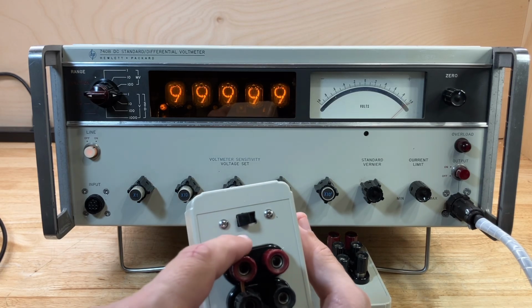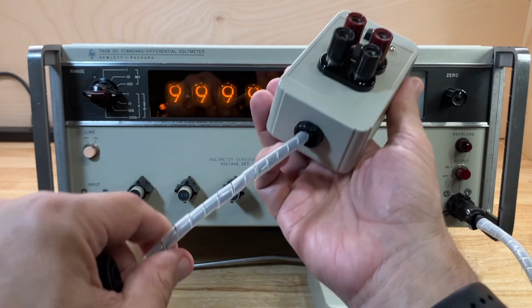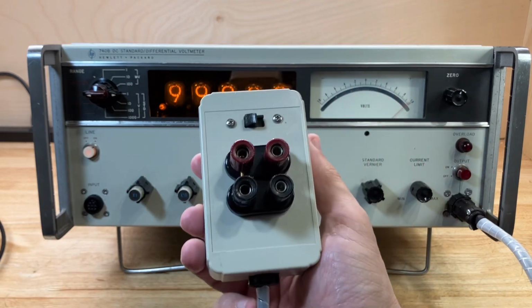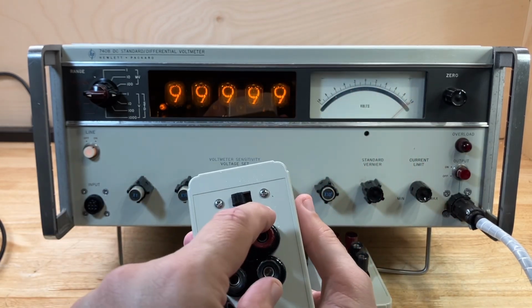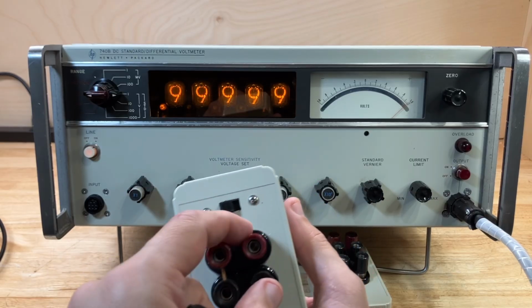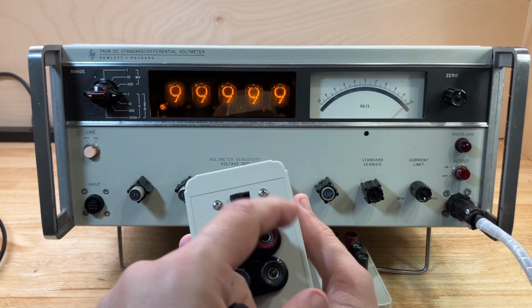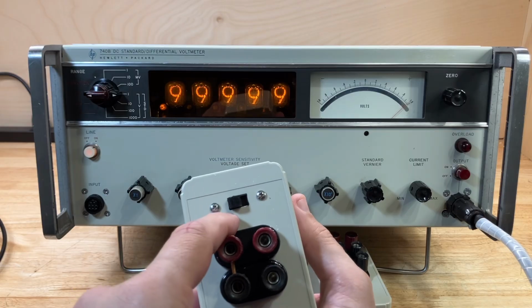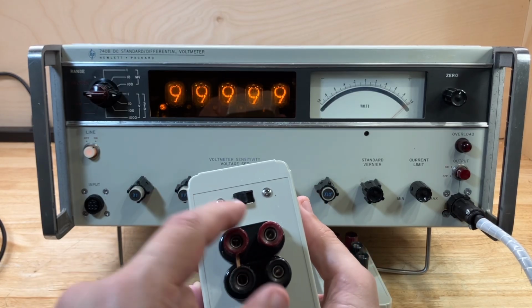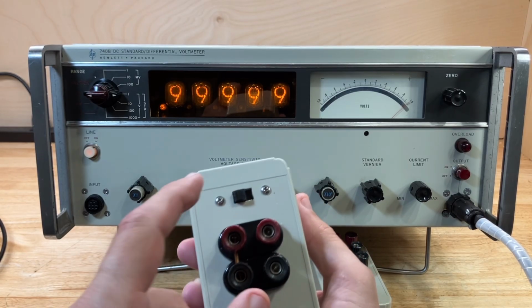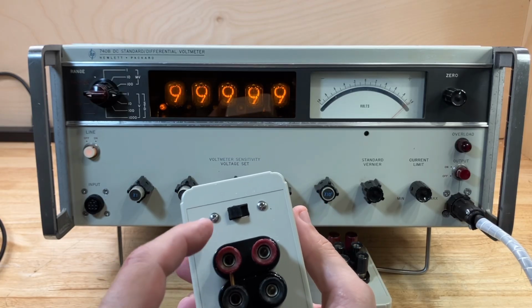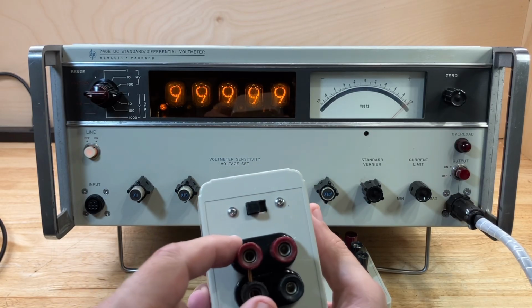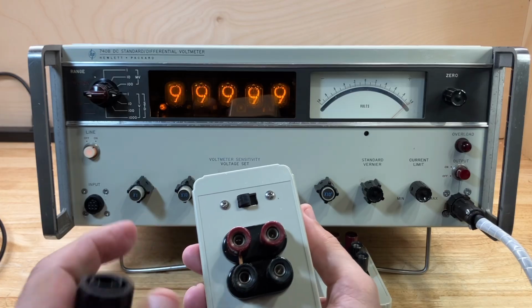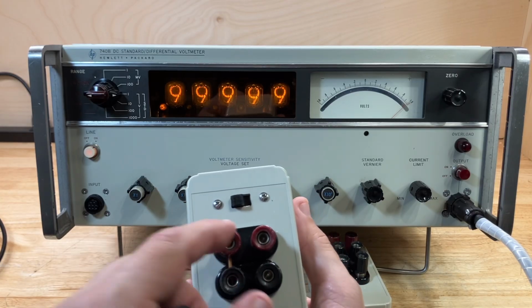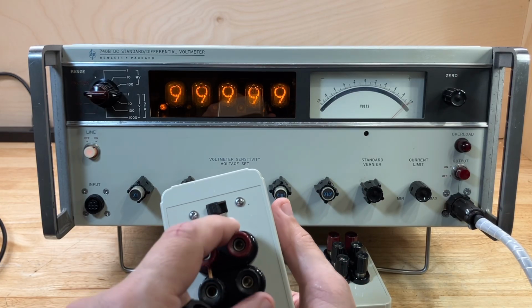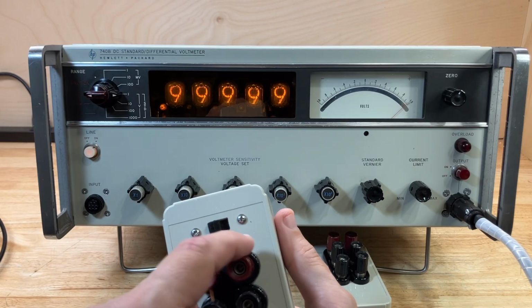noise spikes and so forth, but any stray capacitance, even in the cable, can hold a charge. And because you can measure up to 1,000 volts with an infinite input impedance, that stray capacitance and the capacitor that's in here as well can hold that 1,000-volt charge.